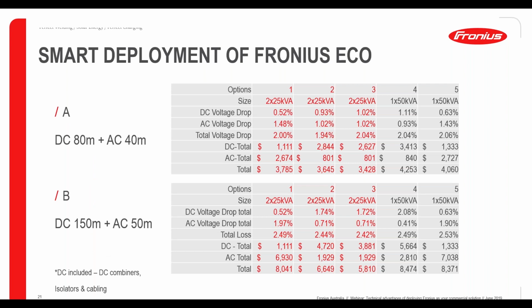One thing that's come up as obvious is that using inverters on the roof and having longer AC runs is typically not cost effective, because when we run DC, we have typically higher voltage, which then allows us to maintain smaller voltage drop with smaller cables. Options 1 through 3 are Fronius based options. We could see that some of the options are more cost beneficial than the others.